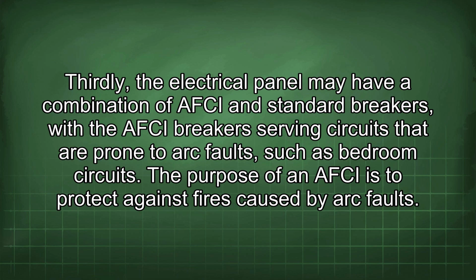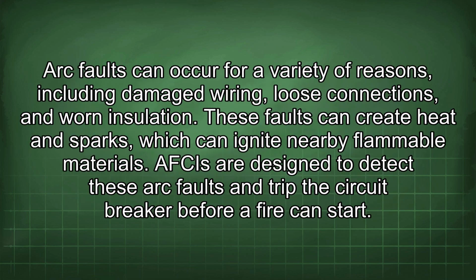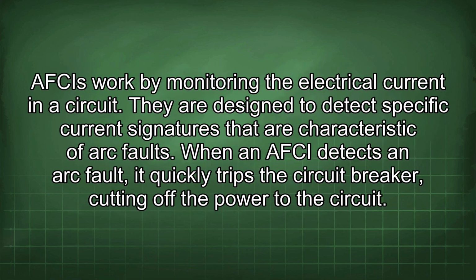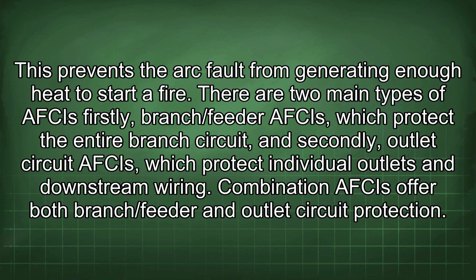The purpose of an AFCI is to protect against fires caused by arc faults. Arc faults can occur for a variety of reasons, including damaged wiring, loose connections, and worn insulation. These faults can create heat and sparks, which can ignite nearby flammable materials. AFCIs are designed to detect these arc faults and trip the circuit breaker before a fire can start. AFCIs work by monitoring the electrical current in a circuit. They are designed to detect specific current signatures that are characteristic of arc faults. When an AFCI detects an arc fault, it quickly trips the circuit breaker, cutting off the power to the circuit. This prevents the arc fault from generating enough heat to start a fire.